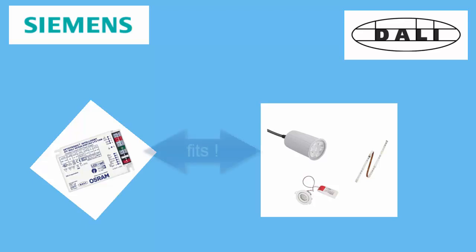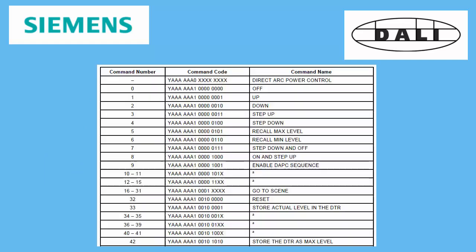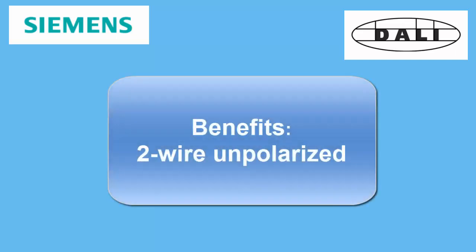The main benefit of DALI is that each lamp has the best possible electronic ballast to operate it, because normally manufacturers have developed both to suit each other in the best way. The control of dimming values is performed by a standardized protocol. Another benefit — mainly for contractors who have to install the wires — is that DALI uses an unpolarized two-wire communication line, which can be wired together with the mains.